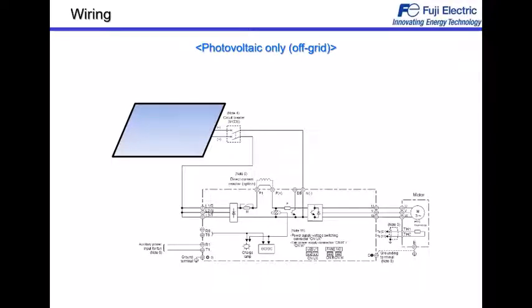Wiring. This is the wiring for off-grid when we just have solar panels supplying the system. In this case, first, the panel poles should be isolated. The positive should go to the entrance of the drive, 3 lines, L1, L2, L3, and the reason is to split the current among the diodes. So not one diode is taking all the current from the panel. So we are using the diodes at the entrance, and the negative goes to the negative of the DC bus.